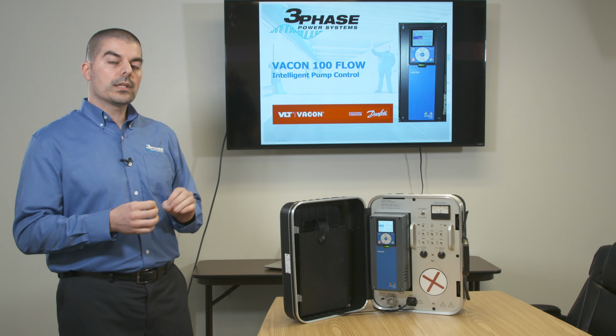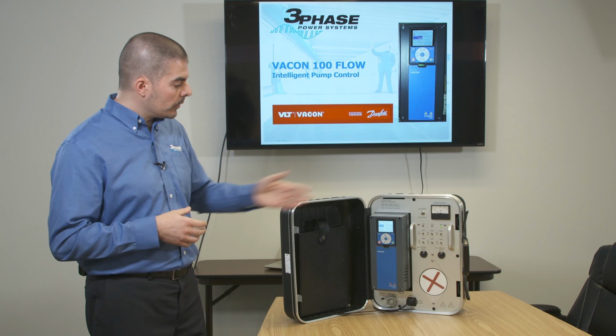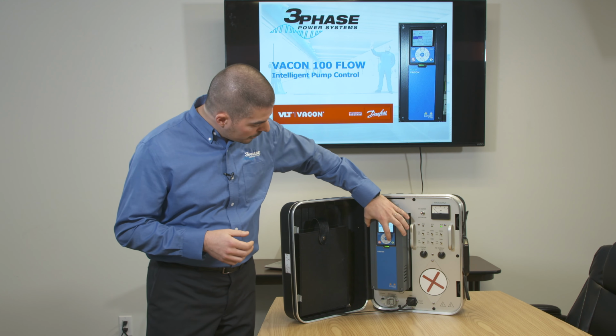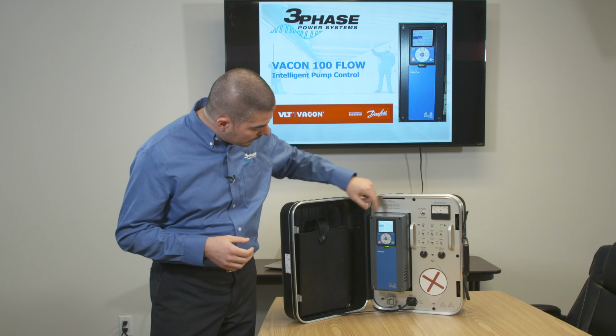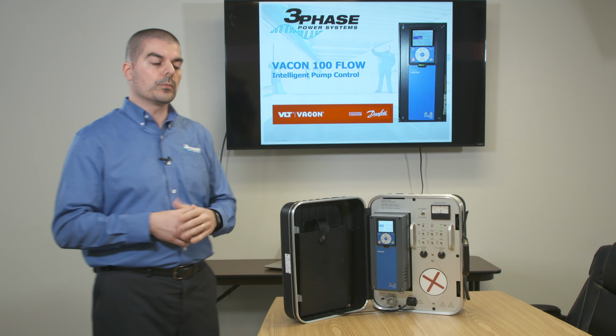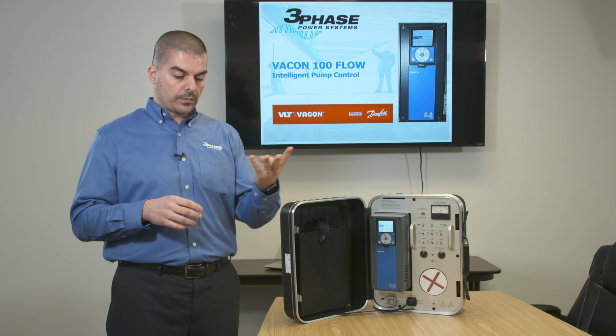When you look at the keypad here, I want to point out that most drives you have to scroll through in order to navigate and monitor different values. Now with this keypad, we can actually monitor up to 9 different things all at the same time. We can monitor 4, 6, or 9 things all at the same time, depending on the matrix on the screen. But here is an example. This is a traditional example. We have, for example, a pumping application. And what are the things that are important for the client to monitor?